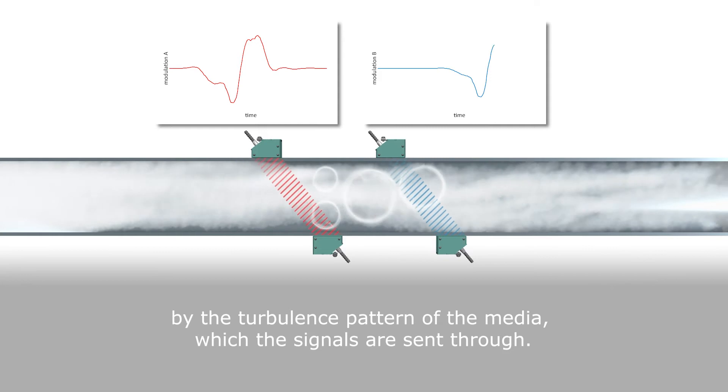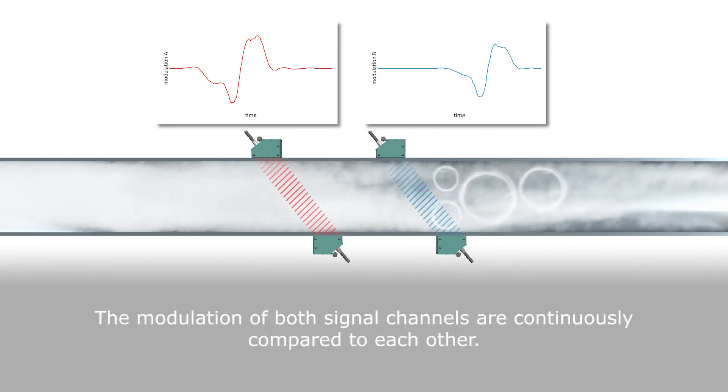The turbulence pattern then flows through the pipe to transducer pair B's ultrasonic channel, modulating the ultrasonic signal of channel B in the same way as that of channel A.